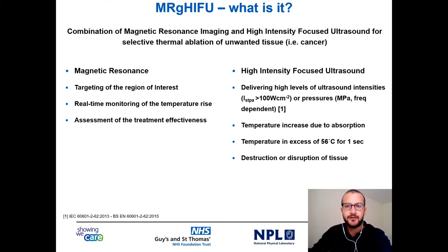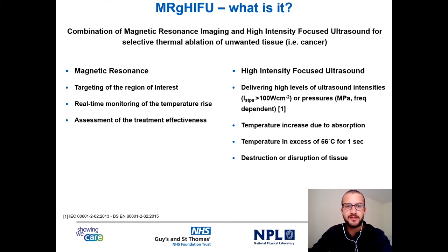MR-guided HIFU is the combination of magnetic resonance imaging and high-intensity focused ultrasound for thermal ablation of unwanted tissue. An HIFU transducer delivers a high level of ultrasound intensities to increase the temperature in the tissue. When the temperature exceeds 56 degrees for one second, there is irreversible damage of the tissue.